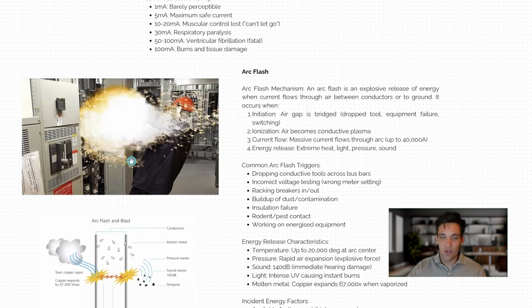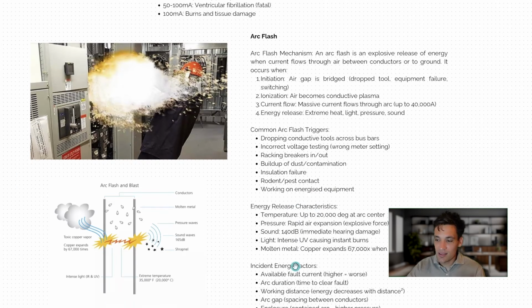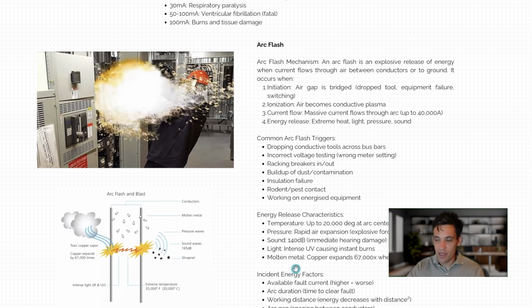The same thing happens in circuit boards where there's a fault and there's an arc between a live conductor and the grounded frame. Where do we often see arc flash triggers during electrical installations? It happens when people drop tools across bus bars, when there's incorrect voltage testing, when they're racking breakers in and out. Often when you disconnect live circuit breakers, there's an intentional arc that develops. You can get it when there's a buildup of dust and contamination, which bridges the gap between a live and ground conductor. Failures of insulation, or maybe rodents or pests, can bridge the gap and cause an arc flash. Or generally, the risk occurs whenever there's work around or on energized equipment.